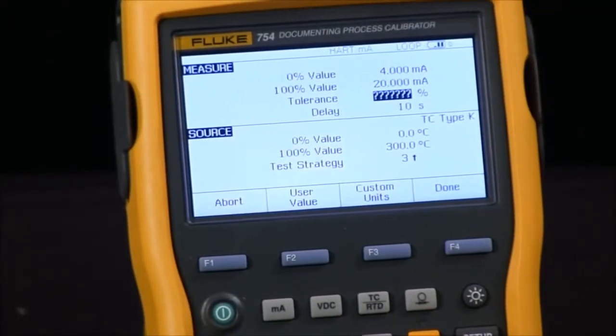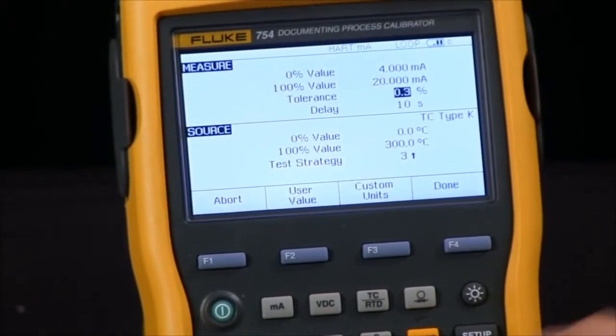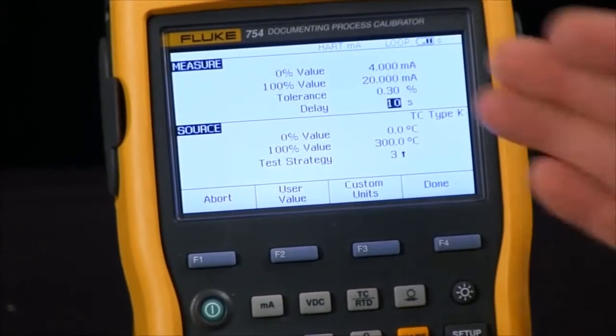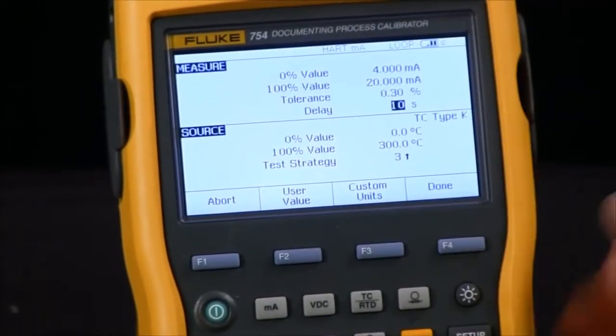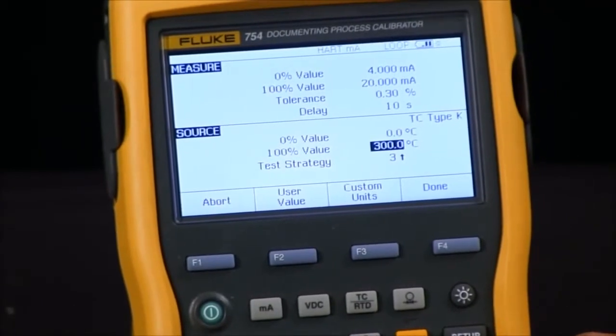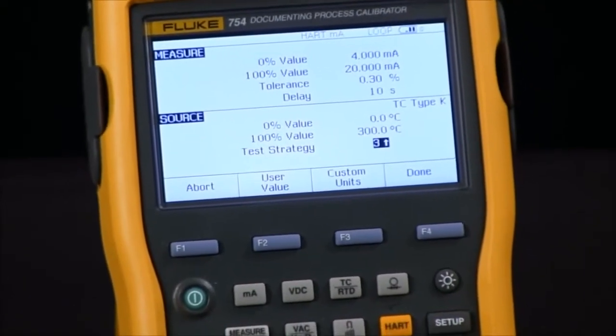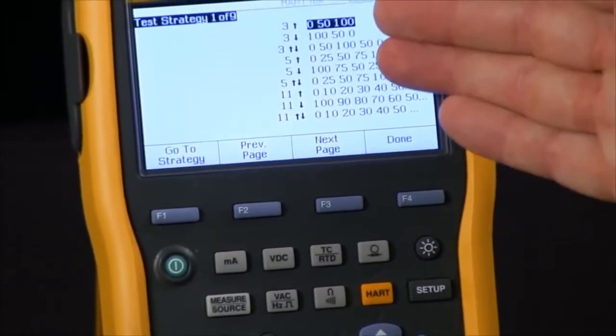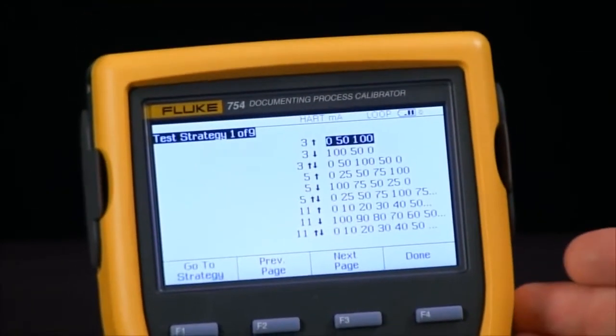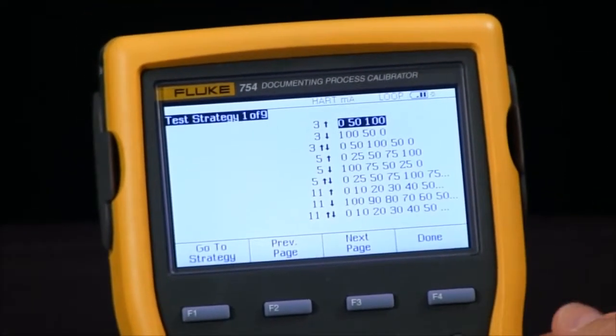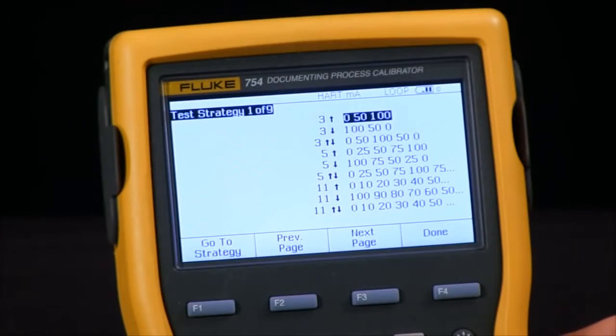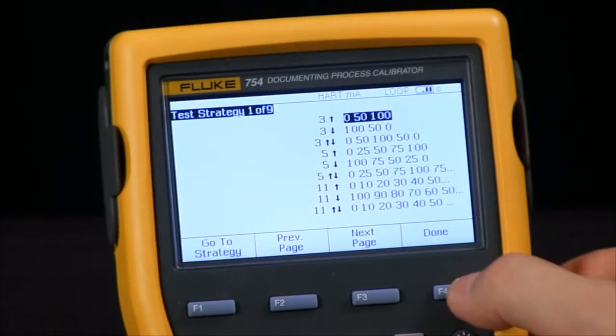I will set my tolerance. We'll just select 0.3. My delay, I can set to anything. I will leave it at 10 seconds. And there's my 0% and my span values. And then what kind of test do I want to do? I have a selection from a 3 up, 3 down, all the way up to an 11 up and down. Or I can select any specific test called out by the manufacturer or by my specific process.